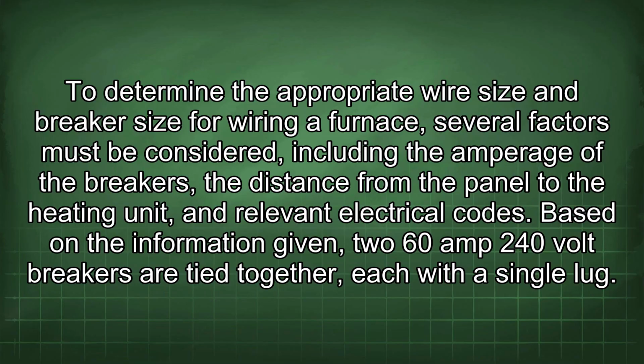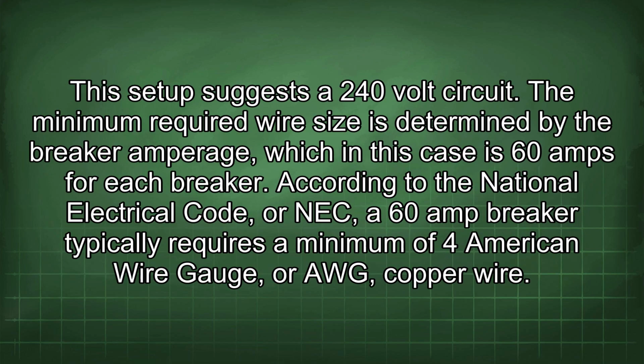To determine the appropriate wire size and breaker size for wiring a furnace, several factors must be considered, including the amperage of the breakers, the distance from the panel to the heating unit, and relevant electrical codes. Based on the information given, two 60-amp 240-volt breakers are tied together, each with a single lug. This setup suggests a 240-volt circuit.